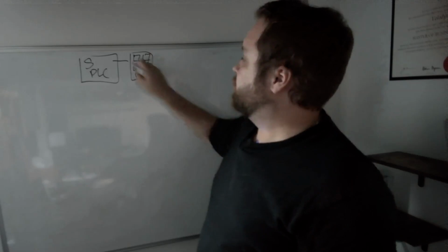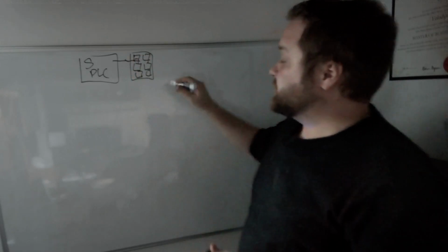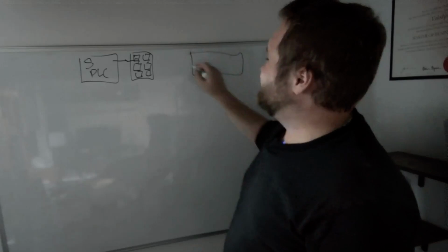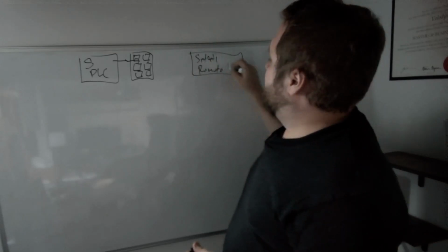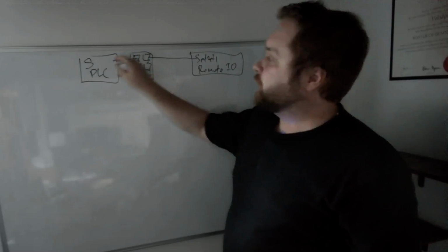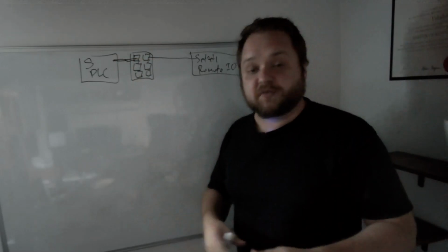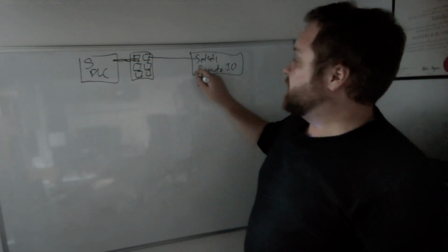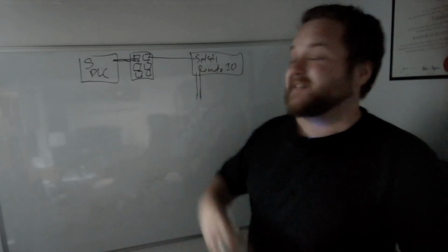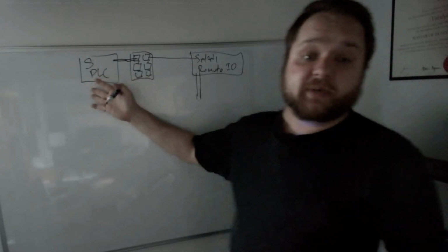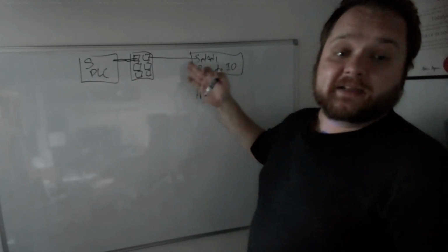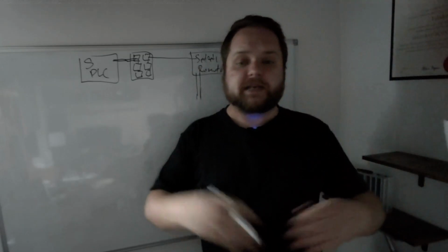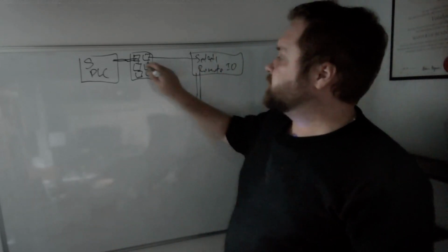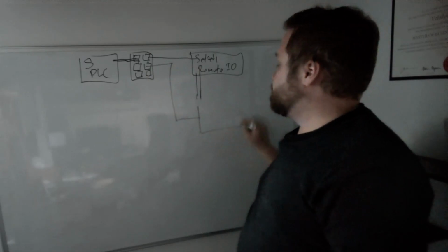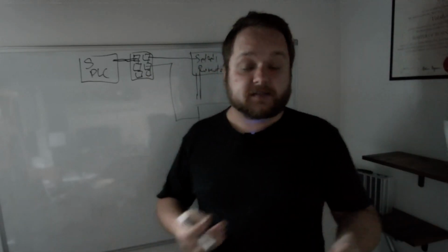I'm just going to very quickly illustrate this. And this PLC is going to talk to some kind of a safety rated, so safety remote I/O. And this is going to obviously prioritize the traffic. It's going to shut down if it doesn't receive a packet after a certain amount of time. But this is also going to allow you to create a more distributed environment where you have a safety PLC maybe inside of the cabinet, and then you're looking to have some I/O that is going to be safe, specific for a different area. So there's going to be a lot of different options where you can create a system that is going to be quite a bit more complicated than what we've discussed a little bit earlier.